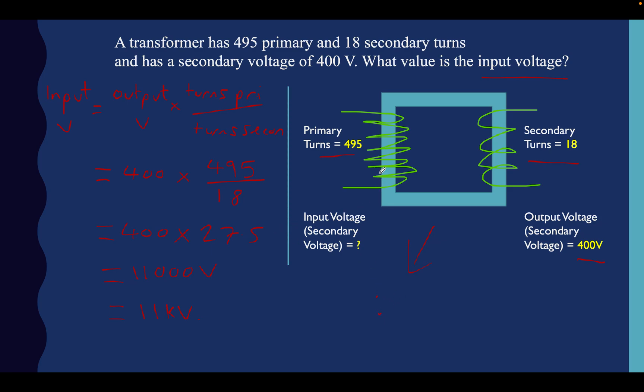We've already calculated that really, by doing 495 divided by 18. We know that the ratio is this number here. That's why I said we'll talk about it in a minute. So the ratio is going to be 27.5 to 1. Because if we do 27.5 multiplied by 400, we're going to get 11,000, which is stepping that voltage up like that. It's a step down transformer. And if you do 495 divided by 18, you get 27.5. So that's our ratio. The step down transformer ratio is 27.5 to 1, and we've calculated our input voltage over here.